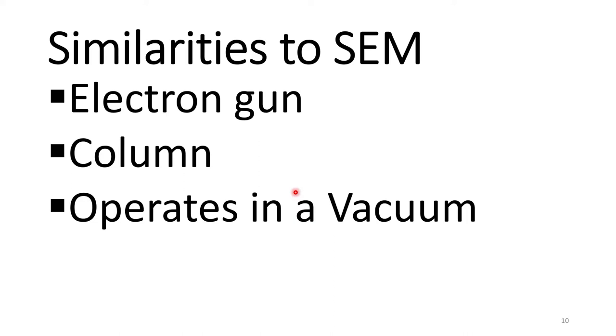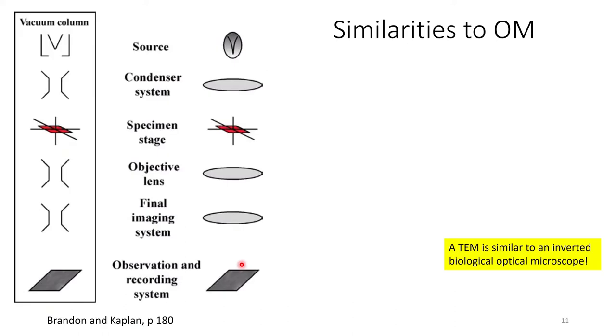Similarities to scanning electron microscopy: you have an electron gun, a column, and it operates in very high vacuum. Similarities to optical microscopy: if you look at this schematic from Brandon and Kaplan, we have our electron gun, different apertures, where our specimen lives, magnetic lenses, and our recording plane. A TEM is basically just an inverted biological optical microscope. In fact, the design of the TEM was based on a biological optical microscope because that's all the early designers had to go on.